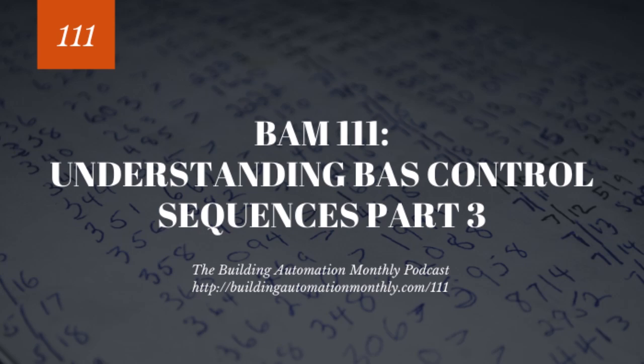Then there's, as I mentioned, load with FLA. There's the PID of the chilled water supply temp set point. So there's that PID output. You can use that as well. And then, as I mentioned, there's decoupler and decoupler position and the GPM of the primary secondary. So those in themselves are not that difficult to code. Once you learn the design pattern to code those different scenarios, it's really easy.